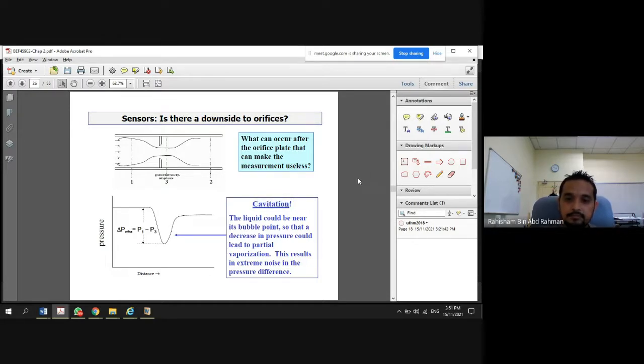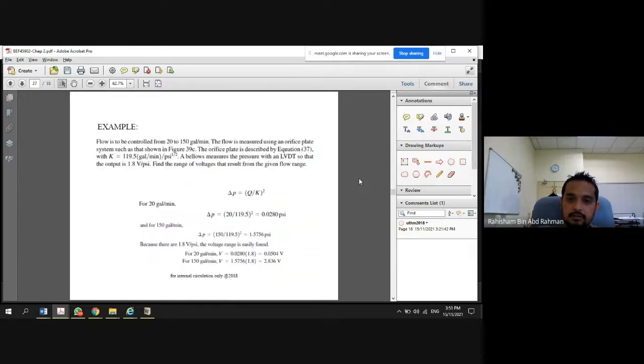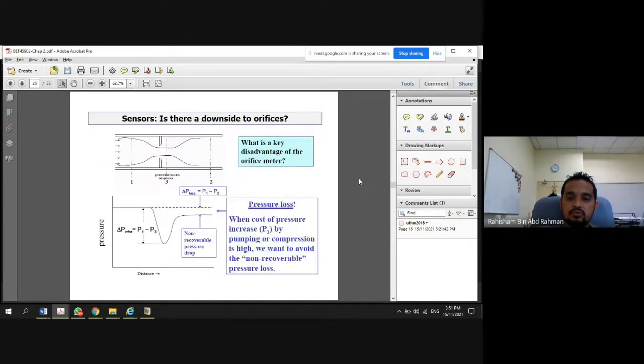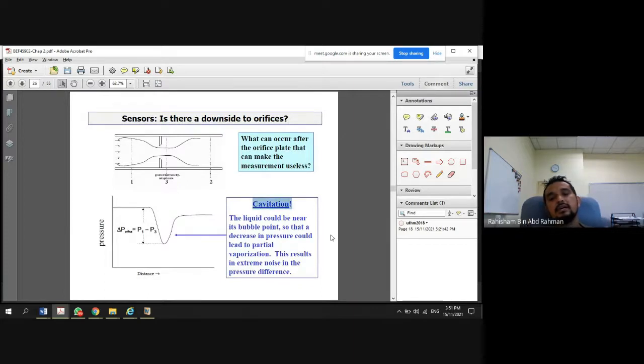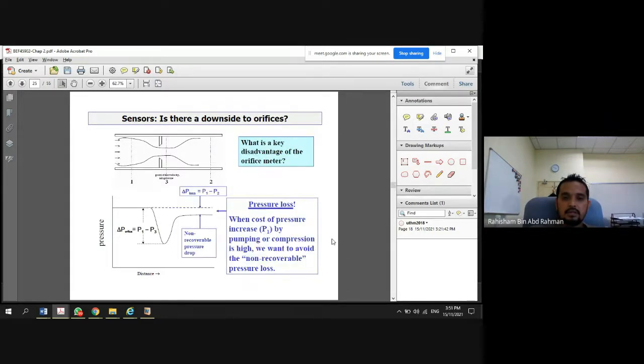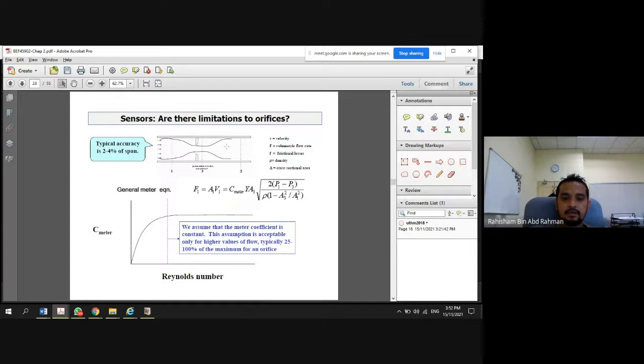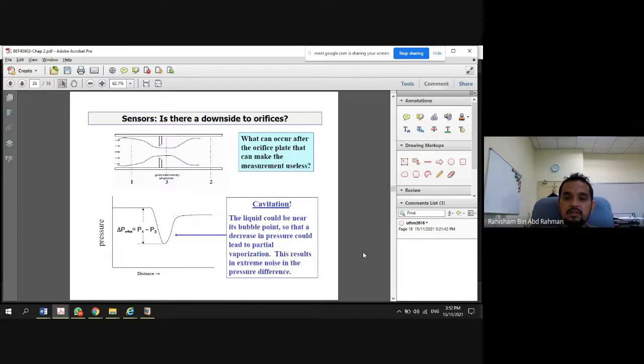Okay, these are two major downsides of the orifice plate. One is the pressure loss, and the other one is cavitation. Okay, there are two phenomena related to the orifice plate. And if you want to add some more, the third one will be that this only works for higher values of flow. Kalau dia rendah, kita dah tak boleh pakai. If the flow rate is very low, orifice plate may not be a good option for engineers to incorporate in their system.